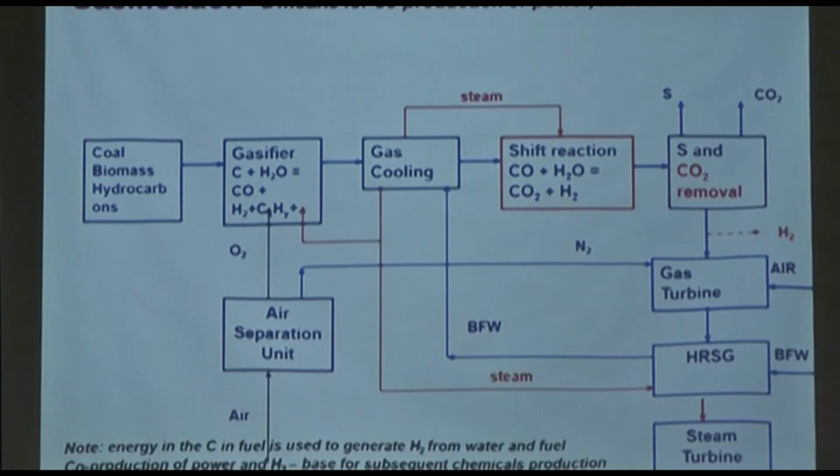And when you are cooling the gas, you can actually generate steam, because if you are cooling the gas indirectly by using water, it will generate steam. Part of that steam can be used in the system, and then the other part can go for power generation if you want to.